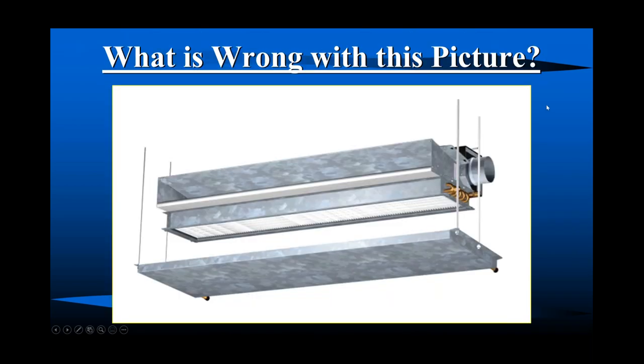Because it already has, right? What's wrong with this picture? This is a picture from an installation manual from a number of years ago, right? Here's our active chilled beam. Here's our primary air coming in from our DOAS unit. And we have to induce, there's an induction unit. We have to induce air up across this coil and out the sides. Well, what's blocking the movement of air up? Well, this condensate pan, and it's supposed to be sensible only. This is the kind of stuff that happens without balancing.